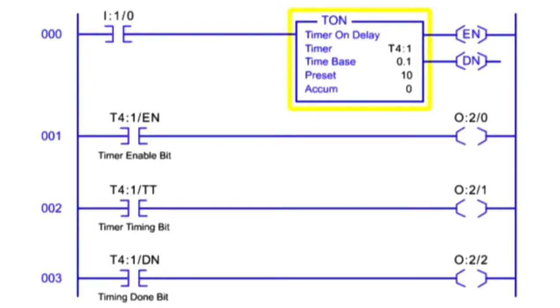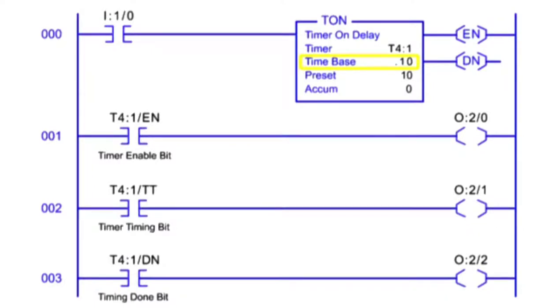The Timer On Delay instruction is used to turn an output on or off after the input has been on for the preset time interval. The timer requires user input data that consists of a preset value and a time base. The time base of the timer instructions is expressed in seconds. Common time base values include 0.01, 0.10, 1.0, and 10 seconds.